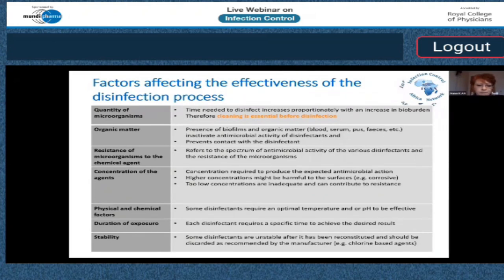sort of an infection or sort of a reaction to the microorganisms. We look at the type and the concentration that you need to use. So if it tells you it kills 99.9%, but you have to expose your instrument for 60 minutes, you will definitely know that this is not the right one for you, even though it says it kills 99.9%, because we don't have the time to expose our instruments for 60 minutes to have them safely rendered for next use.